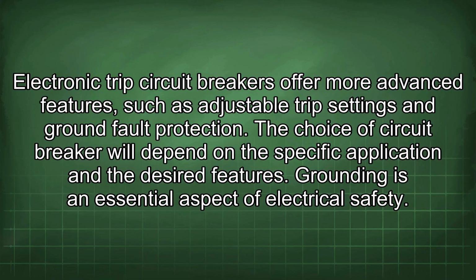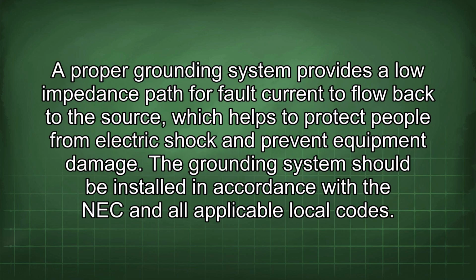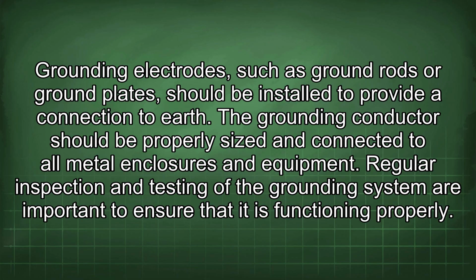Grounding is an essential aspect of electrical safety. A proper grounding system provides a low impedance path for fault current to flow back to the source, which helps to protect people from electric shock and prevent equipment damage. The grounding system should be installed in accordance with the NEC and all applicable local codes. Grounding electrodes, such as ground rods or ground plates, should be installed to provide a connection to earth. The grounding conductor should be properly sized and connected to all metal enclosures and equipment. Regular inspection and testing of the grounding system are important to ensure that it is functioning properly.